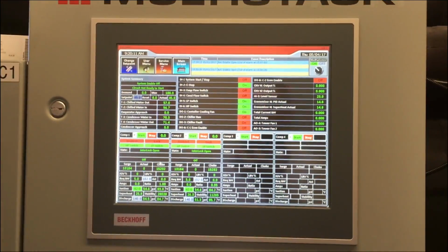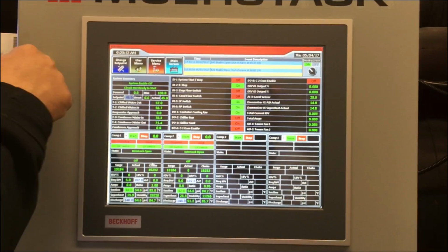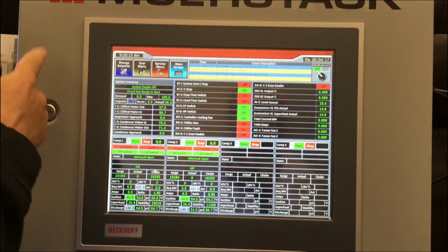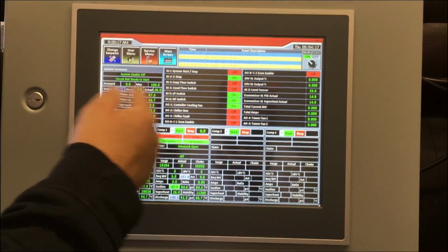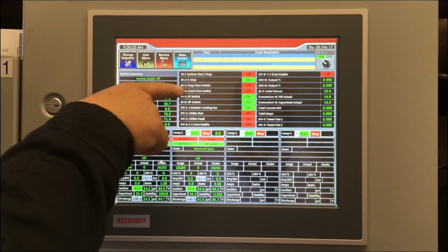Control, the cooling fan is just the little computer fan in the back of the cabinet here. It turns on and off based on temperature. Chiller run, chiller fault, and economizer enable. Now chiller fault says on right now because we're not seeing flow.